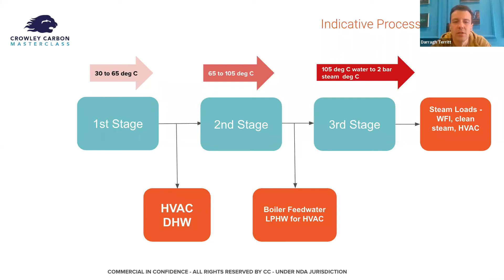At the intermediate stages, you can draw off heat after the first and second stage to provide the lower intermediate temperatures required to supplement HVAC, AHUs, domestic hot water, and potentially boiler feed water. So this is really an example of a configuration that can make a huge impact on your scope 1 emissions on site. Where we've used this in the past, we've seen up to 85% of gas or oil consumption being reduced, so decarbonizing significantly for those clients. If you can go to the next slide, please, Carl.